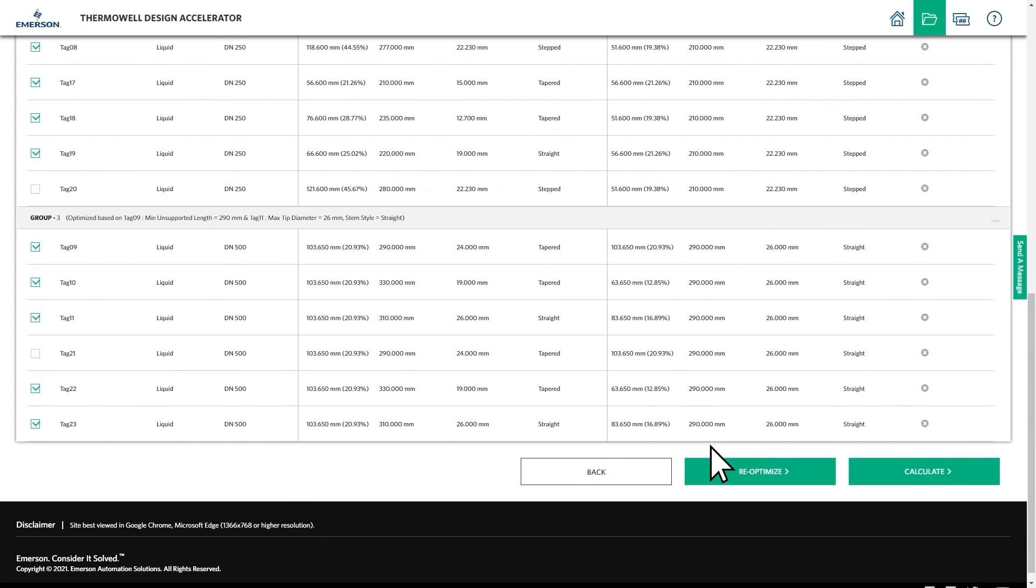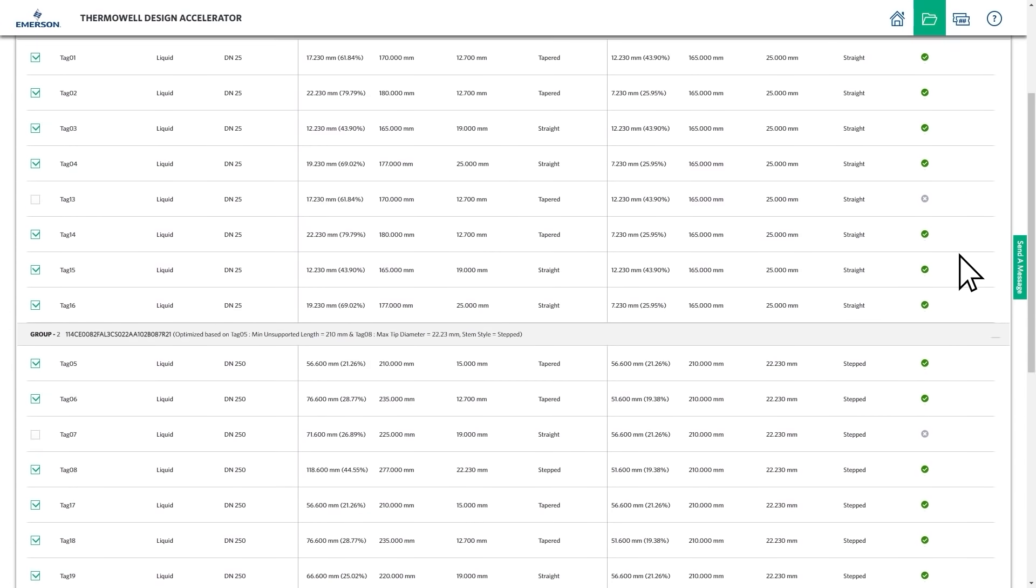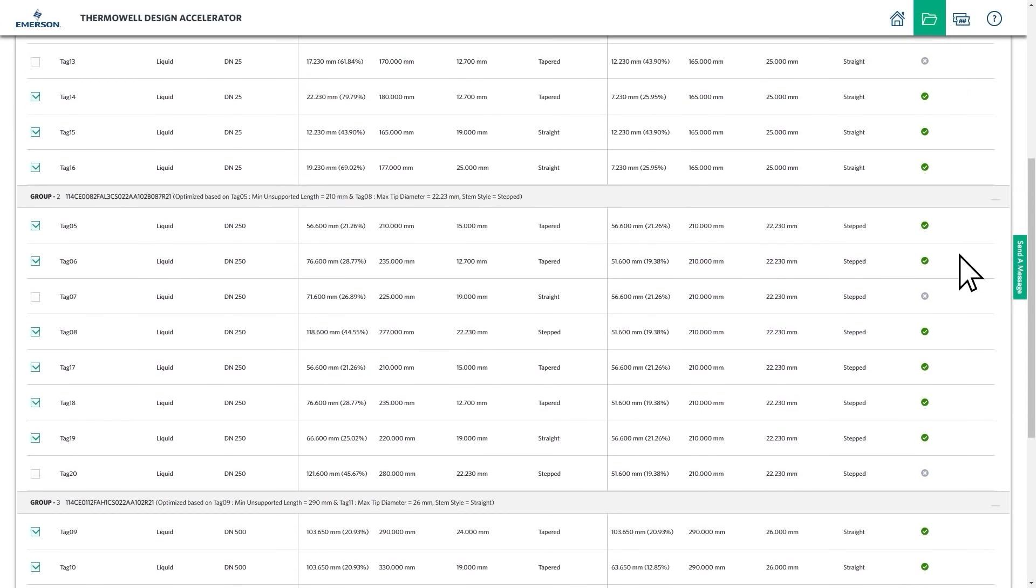Then, click the Calculate button to perform another set of thermowell calculations on the selected thermowell tags. This checks to make sure that the optimized design will work across process conditions for each of the original thermowell tags.